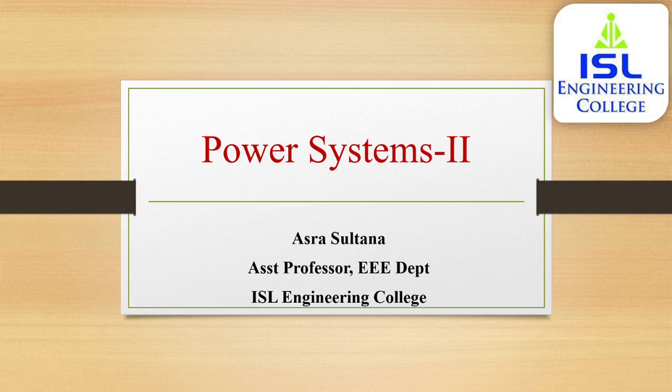Limitation of fault current. When a short circuit occurs at any point in a system, the short circuit current will be limited by the impedance of the system up to the point of fault. If a fault occurs on the feeder at any point F, then the short circuit current from the generating station will have a value limited by the impedance of the generator and transformer and the impedance of the line between the generator and the point of fault. This shows that the knowledge of the impedances of various equipment and circuits in the line of the system is very important for determination of short circuit currents.